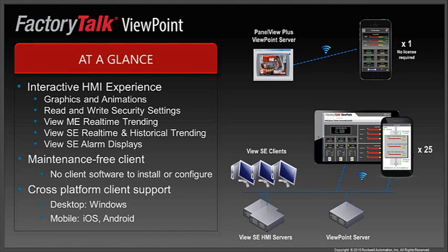While the previous demo was done showing View SE, the publishing process is very similar for View ME. The Viewpoint server is included as part of the PanelView Plus firmware, and one web client is able to connect without requiring a separate license. For View SE applications, multiple clients are able to connect to a single Viewpoint server, and there can be multiple Viewpoint servers in a distributed application.